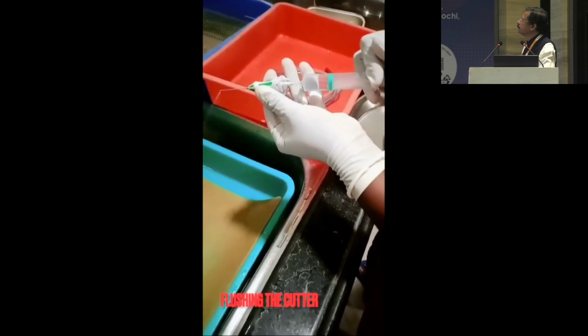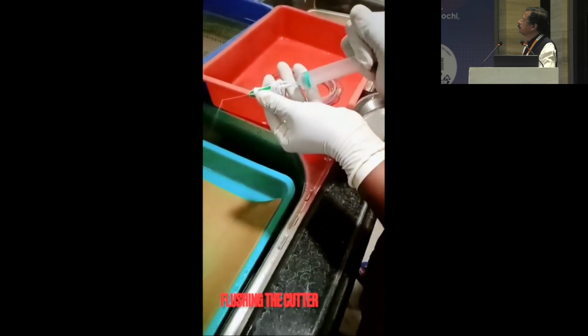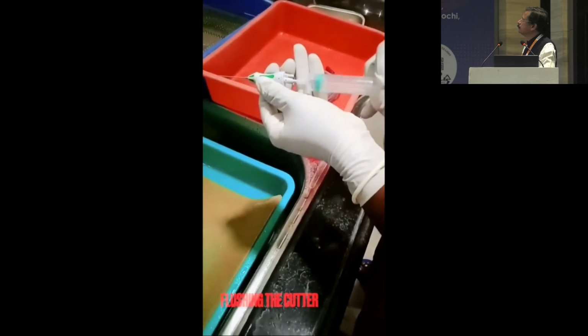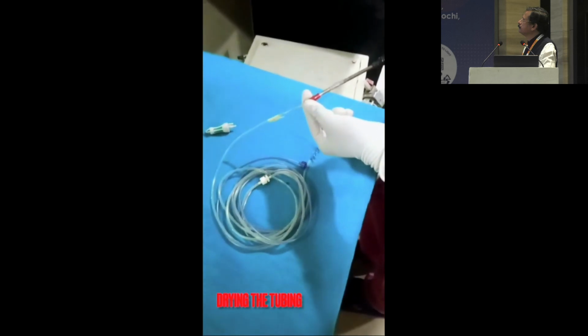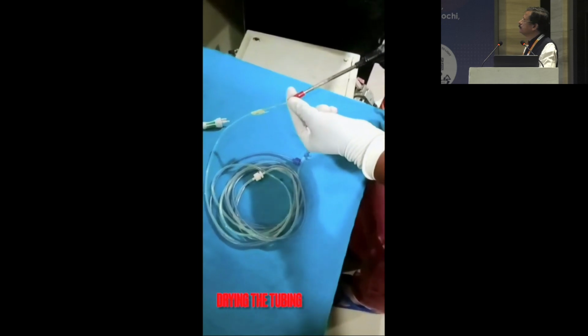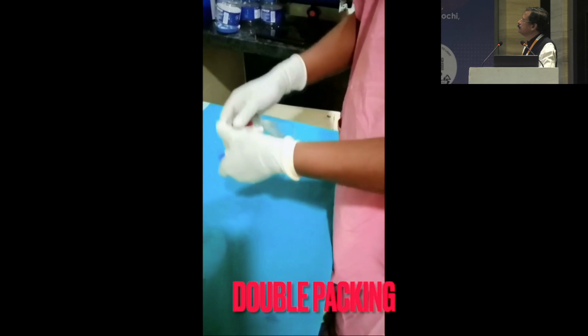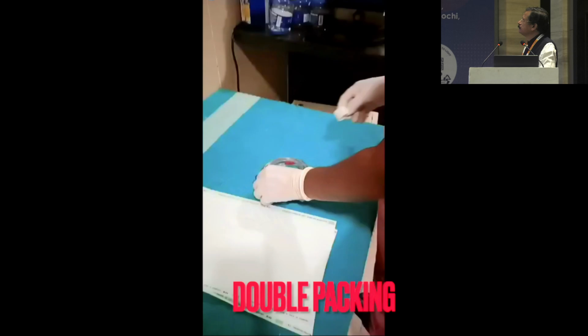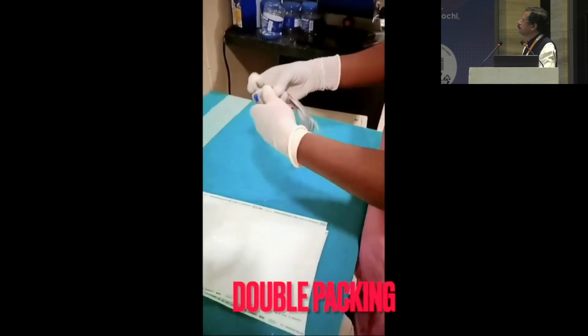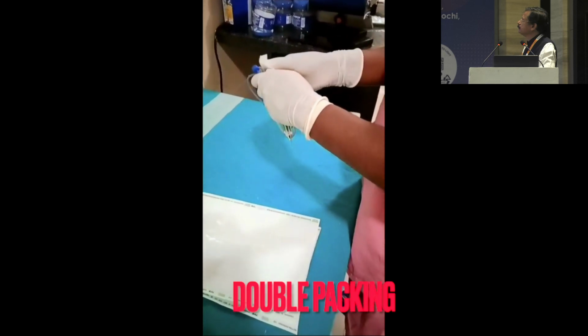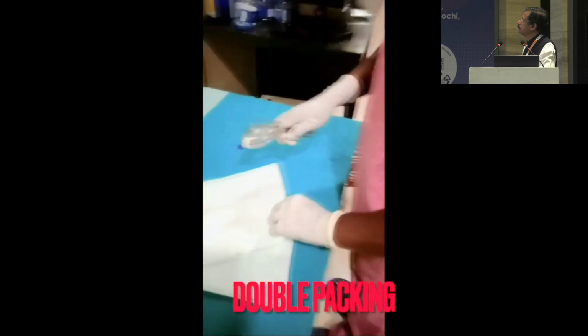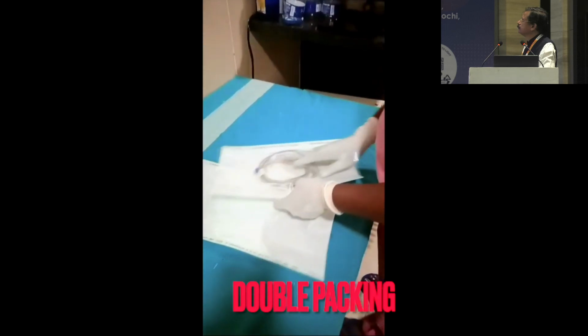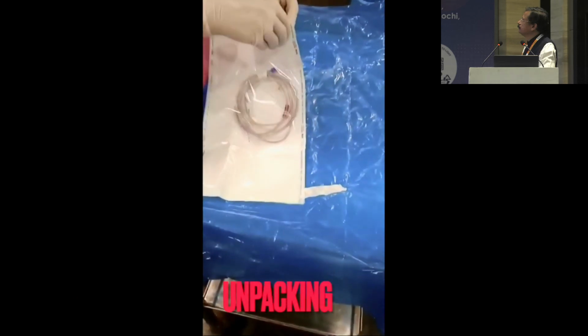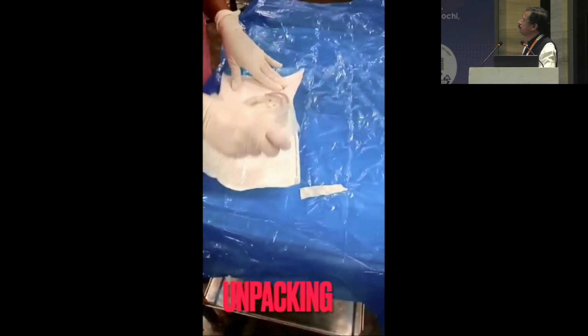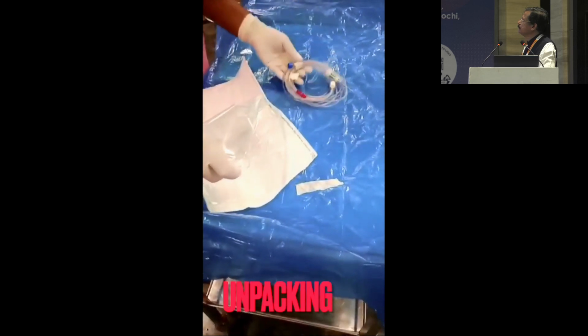Flush the cutter with BSS just to doubly ensure that there is no clogging in the cutter. The tubing is dried with the help of an air compressor. Before packing, the tubing should be folded in a rounded fashion and a bandage applied. Then it is placed in a pouch. The sterilization is usually done by ETO. Because you have applied the sticker, when you are opening it, the tubings won't fall in an unsterile area, and also it will ensure not to damage the cutter. Thank you.